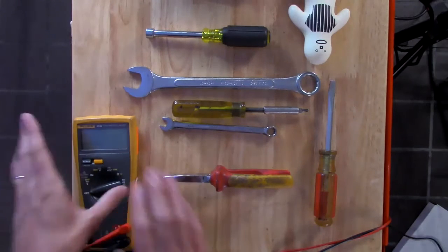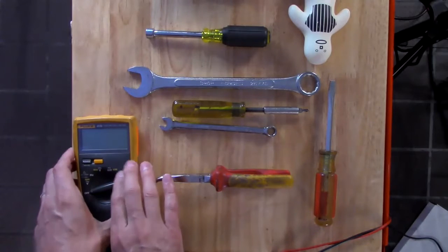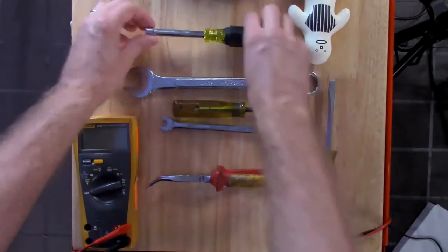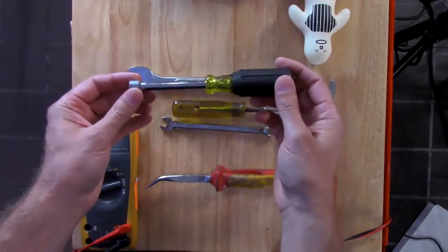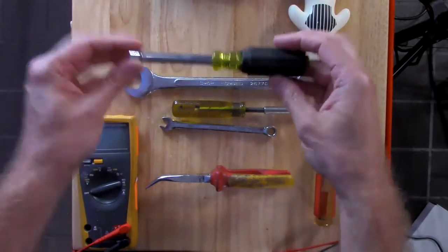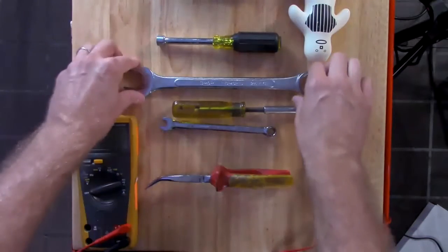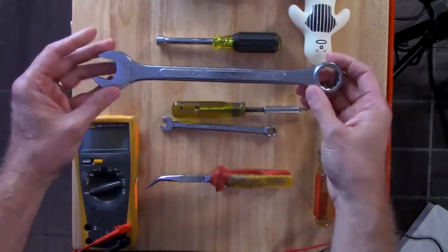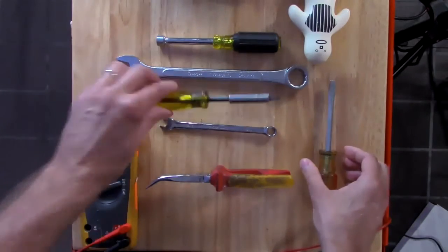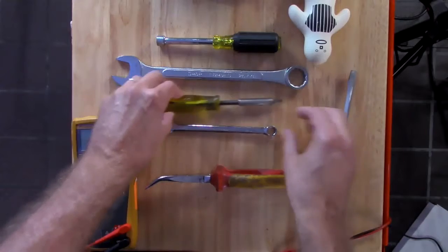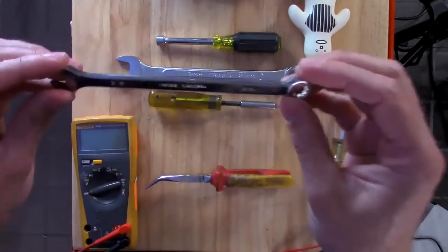So the first thing you want to take a look at, before you even bother going out to the location, is to make sure that you have the right tools. So let's take a look at the tools we would need and the components to take with you so you can get a first time fix rate. So on my left here, definitely need your voltmeter because you can end up checking some voltages. You have your 3/8 nut driver, or you could use a socket ratchet. And then you have your 7/8 wrench, Phillips screwdriver, flat blade screwdriver, another 3/8 wrench, just in case for reach with it.